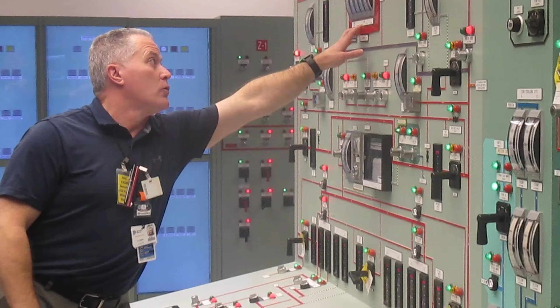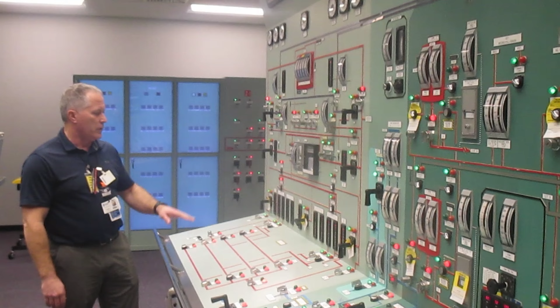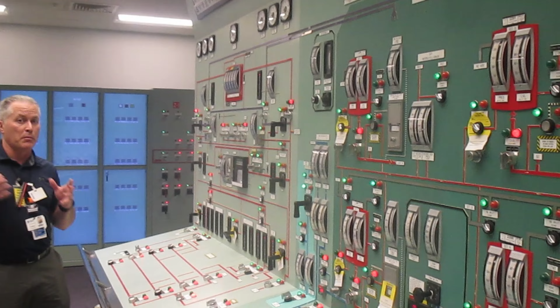The containment can handle up to 40 pounds pressure, so this massive building will get pressurized up to 40 pounds. And that's coming from a big old tank that's outside called the refueling water storage tank. Those will push water in up to about 1,400 pounds. Like I said, that's if there's a break or something that brings pressure down in the primary. And then we have low pressure safety injection pumps. These are that long-term core cooling that I was talking about with those pumps over there. These pumps will pump through those heat exchangers and help to cool the reactor.